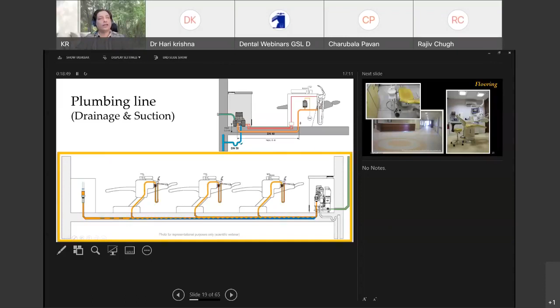Many times I see that people are keeping the suction apparatus in their operatory. Please make sure that if you are keeping suction in your operatory, the exhaust valves are checked regularly, because the air, which carries the issues related to aerosol or infection, will come back into the operatory again. So make sure that the vent goes outside, and that will help you a lot.